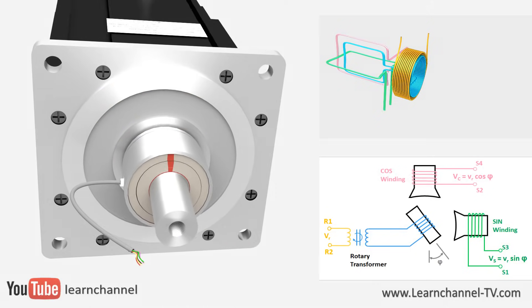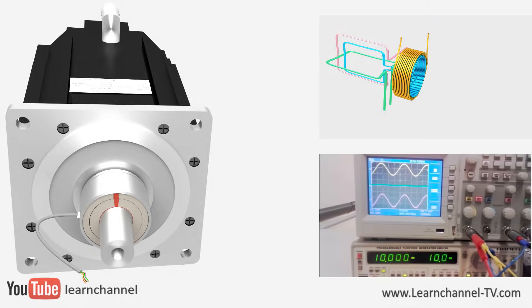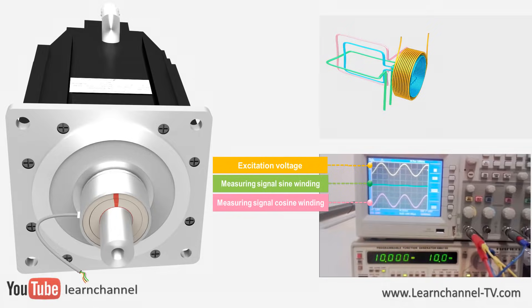So, let's mount this resolver to the motor shaft and apply a high-frequency sine signal to the stator primary winding. The pulsating alternating magnetic field of the rotor winding now induces an alternating voltage in the measuring windings sine and cosine.